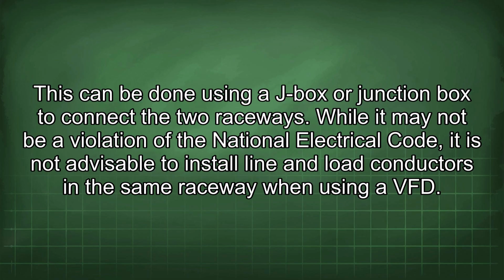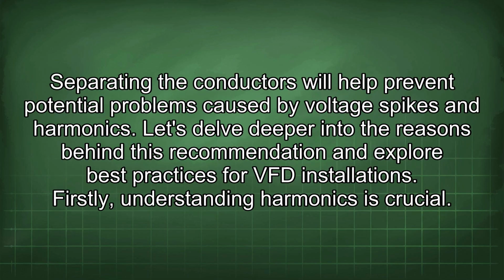While it may not be a violation of the National Electrical Code, it is not advisable to install line and load conductors in the same raceway when using a VFD. Separating the conductors will help prevent potential problems caused by voltage spikes and harmonics. Let's delve deeper into the reasons behind this recommendation and explore best practices for VFD installations.